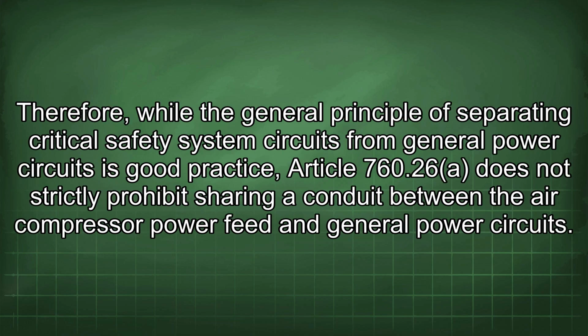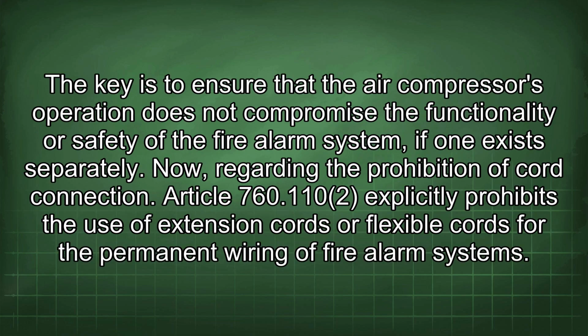Therefore, while the general principle of separating critical safety system circuits from general power circuits is good practice, Article 760.26 does not strictly prohibit sharing a conduit between the air compressor power feed and general power circuits. The key is to ensure that the air compressor's operation does not compromise the functionality or safety of the fire alarm system if one exists separately.